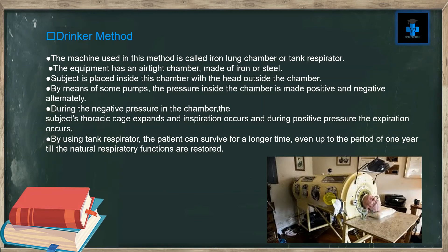The equipment has an airtight chamber made of iron or steel. The subject is placed inside the chamber with the head outside. By means of pumps, the pressure inside the chamber is made positive and negative alternately. During negative pressure, the subject's thoracic cage expands and inspiration occurs; during positive pressure, expiration occurs. By using the tank respirator, the patient can survive for a longer time — even up to one year — until natural respiratory functions are restored.